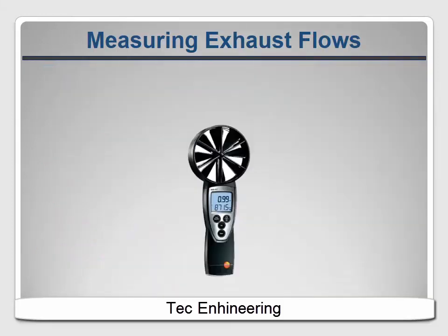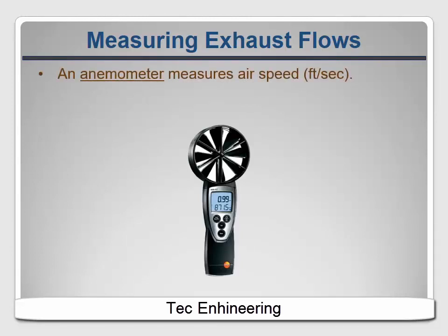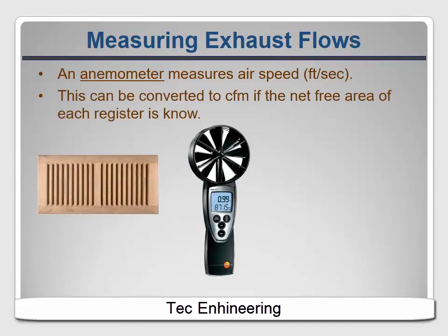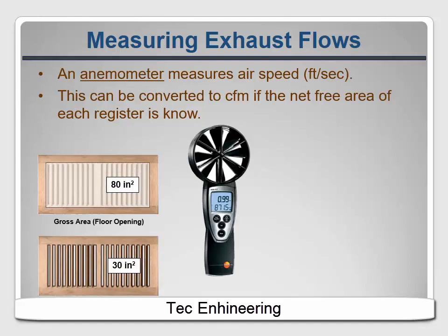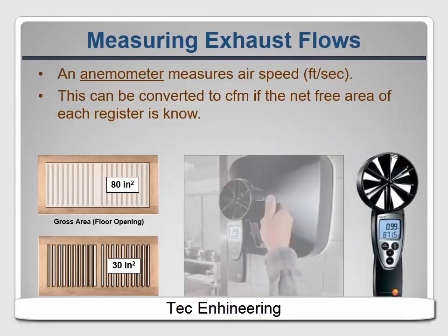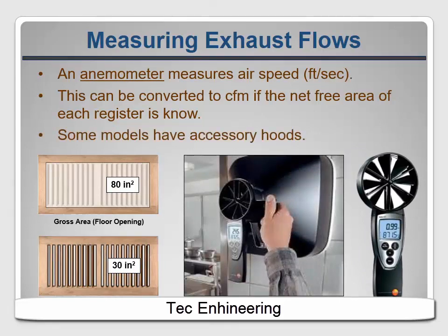The last option is called an anemometer, which has a propeller that measures the velocity of the air going into or out of a register or grill, usually in feet per second. If you multiply that by the area of the opening, you can get the volumetric flow rate, though you have to do unit conversions to get from inches and seconds to cubic feet per minute. You also need to remember that the area of the opening is the net free area between the louvers, not the total area of the register. Basic anemometers can be purchased for under $100. An anemometer made by Testo eliminates the mathematical complications by offering it with a hood attachment that makes the inlet area consistent so it can calculate the CFM for you; it's compact and easy to use and the whole setup costs about $750.